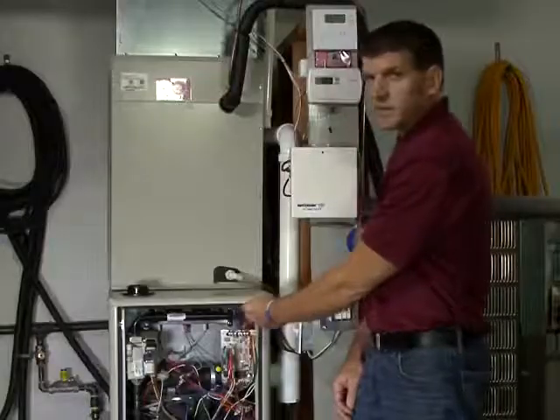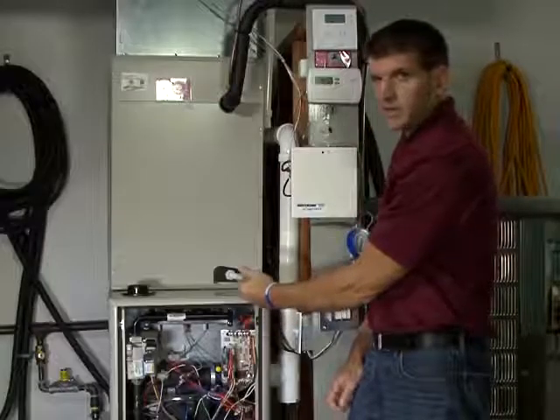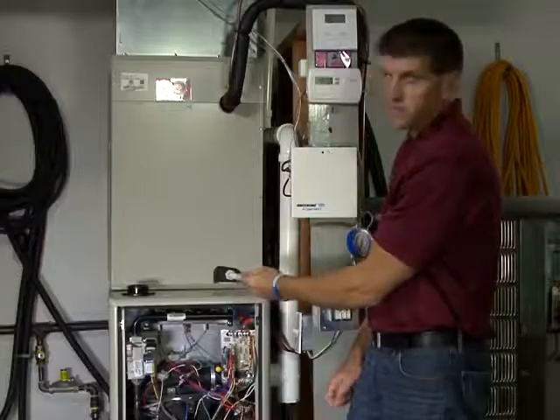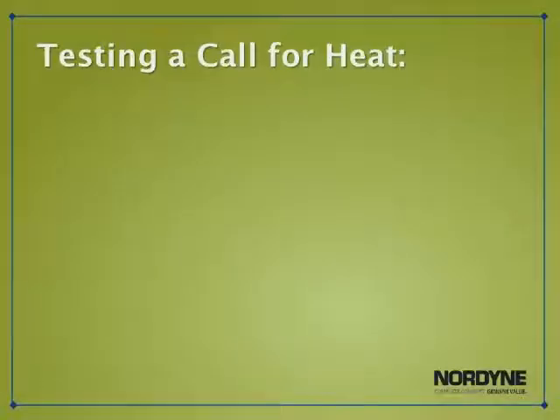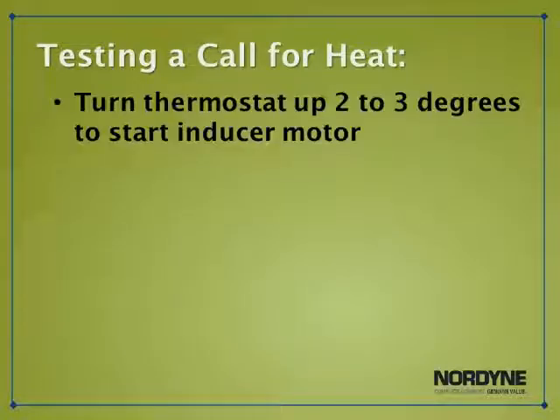Remember, a thermostat is nothing more than a switch. It just sends voltage where it's commanded to. The easiest way to test for this is to turn your thermostat up 2 or 3 degrees on the set point temperature above your room temperature. This will hopefully ensure that your thermostat is calling for heat. At this time, your inducer motor should start and run to start the heating sequence.